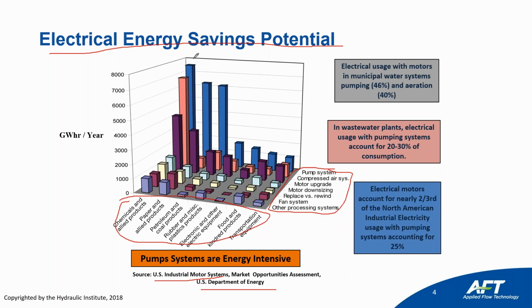So as you can see here, based upon the blue curves right here, in every single industrial system, the pump system is going to give you the best area for saving electrical energy and getting some really good cost savings. So that's where you're going to get your best savings. The next area would be compressed air systems. That's the pink line. Upgrading your motors can sometimes help you save some energy, but not as much as just looking at the pump system itself. Maybe downsizing the motor could help you save some energy. Replacing or rewinding your motors, modifying your fan system, and then evaluating other systems. So fundamentally, the area where you're going to experience the biggest amount of savings is in the pump system itself, and we're going to learn why that is.